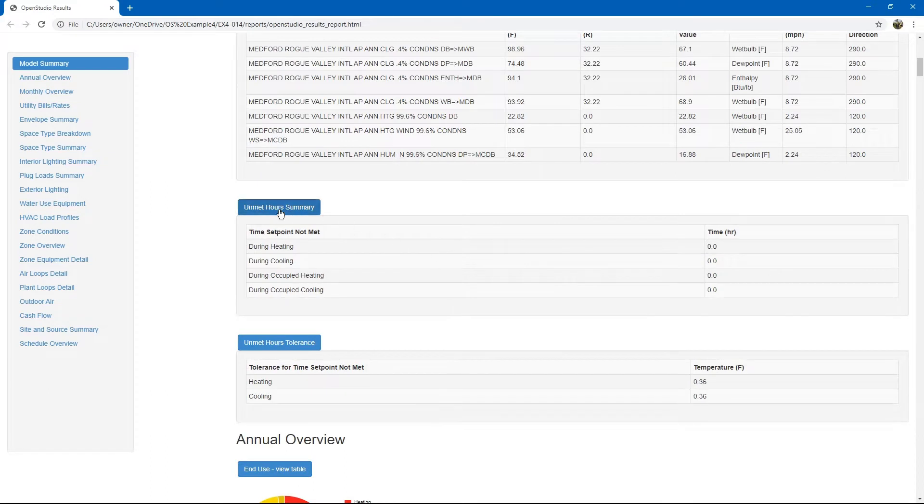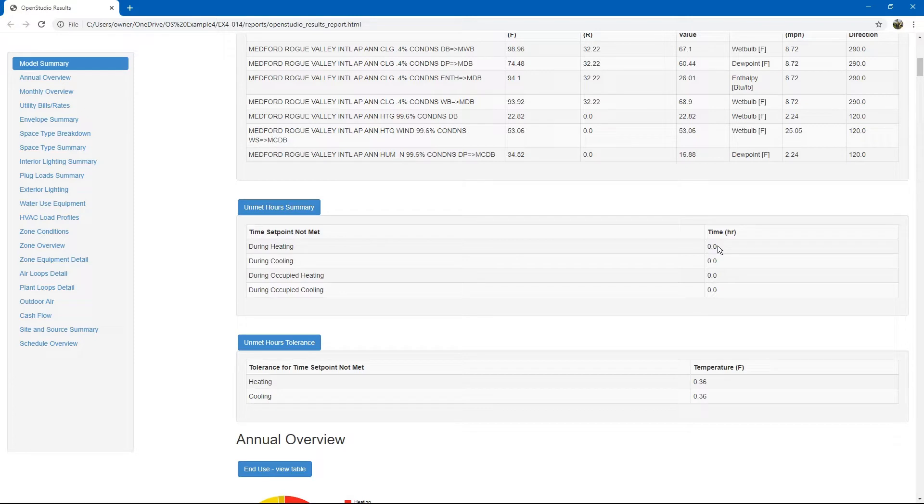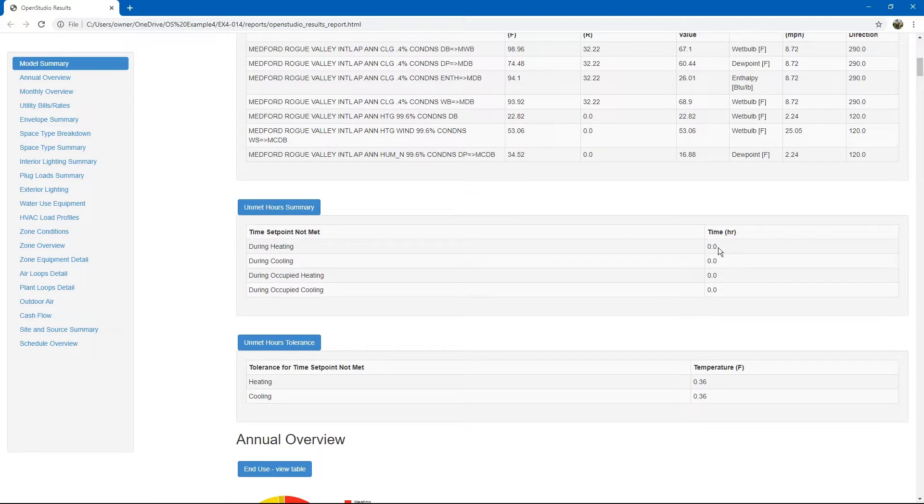Next, there is an unmet hours summary. This is a good summary to look at. If you have unmet hours in your building, it tells you that there might be something wrong with equipment sizing, space loads, or schedules that are overlapping.